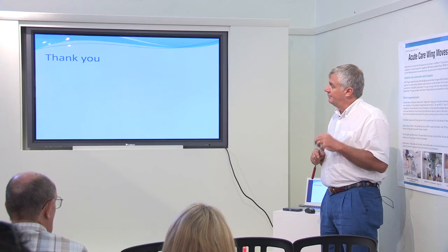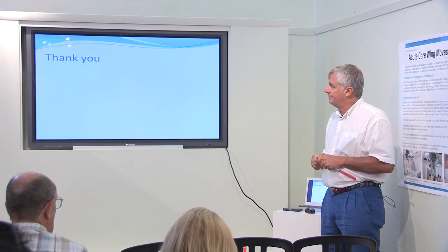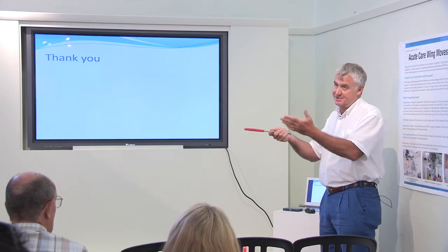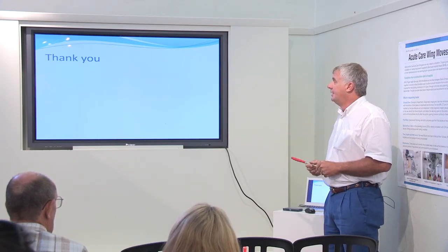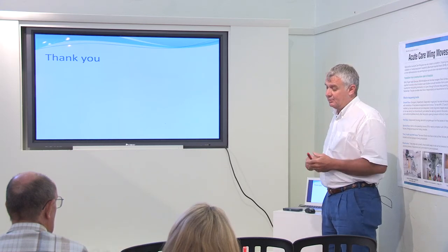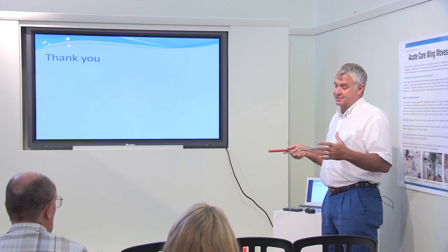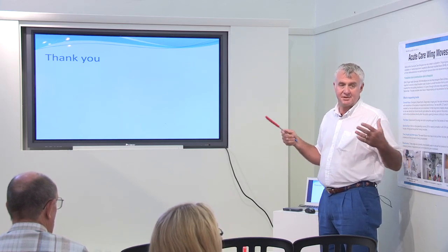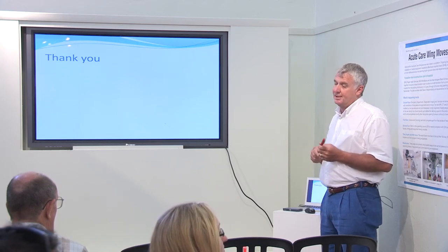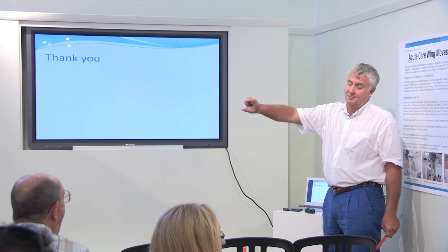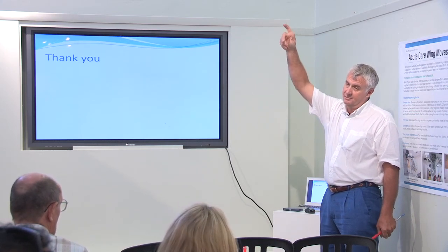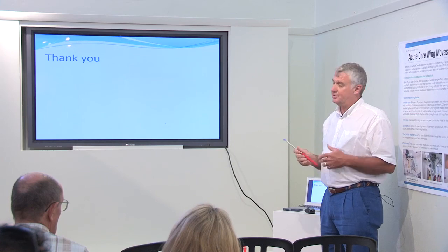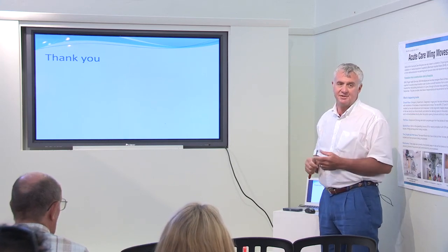Maybe one last point that I didn't talk about that interests people and often gets a question is, does it smell? Because that's what we associate with sewage treatment works, and that's what we see sometimes with these open ones in other countries. Of course it smells, but the fact that it's underground requires that it needs its own special ventilation system. So every single aspect of it is piped to a large carbon filter scrubber that removes a lot of the odors. Then it vents across the car park and into the main building in a duct and all the way up to the top of the new building and is discharged out there. So from that point of view, you don't have some of the unpleasant things that you get with sewage treatment plants a lot of the time.